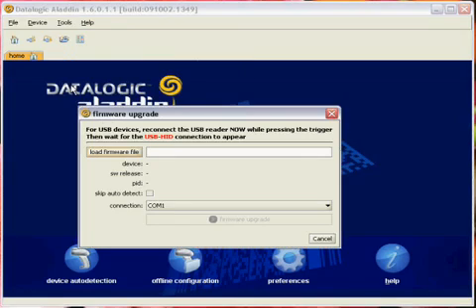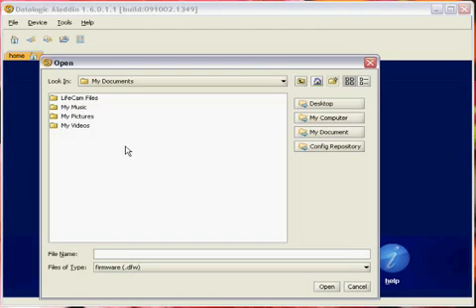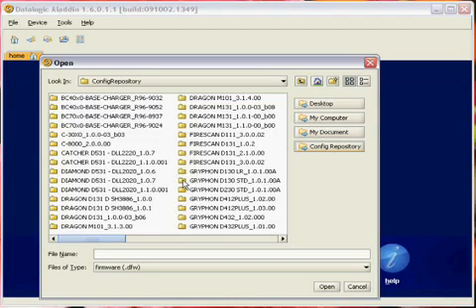Now click on the load firmware file button on the firmware upgrade screen. This will take you to a folder browser. If you're going to use a firmware installed by Aladdin, click on the config repository button on the left. This will give you a list of all the scanners supported by Aladdin.